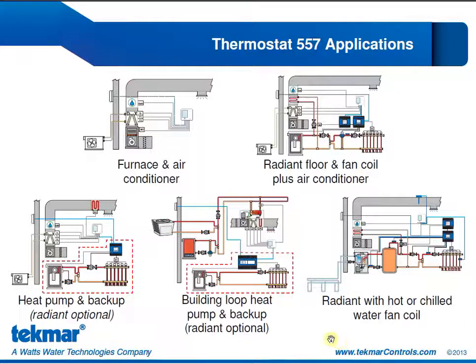Our last heat pump application features a water-to-water heat pump, and as discussed in the first webinar, this requires the pairing of the 557 with the 406 house control. A first stage of heat is provided by the radiant floor, 2nd stage of heat through the fan coil. When we switch over to cooling mode, the fan coil becomes a 1st stage of cooling, and we have the option here of doing radiant floor cooling.